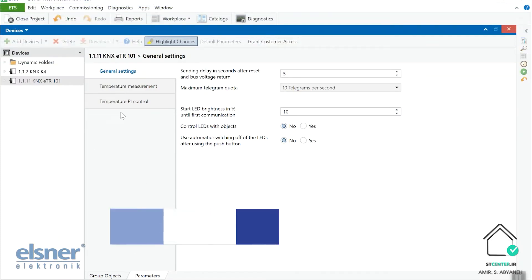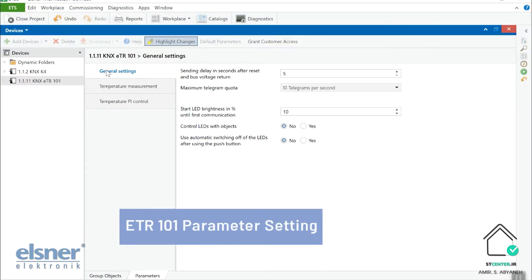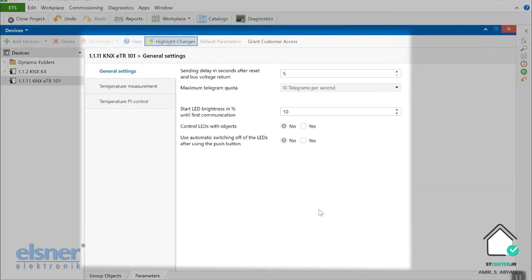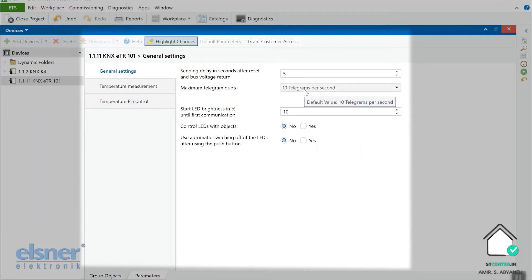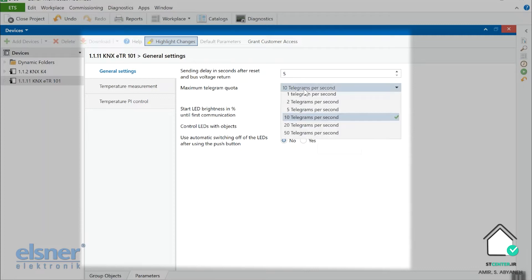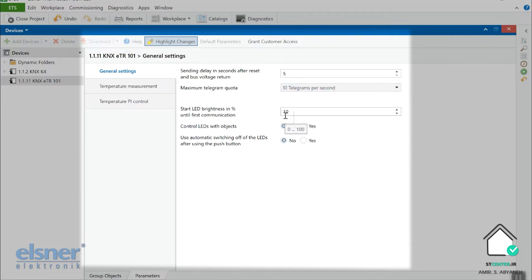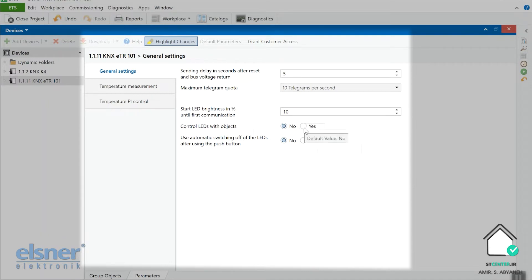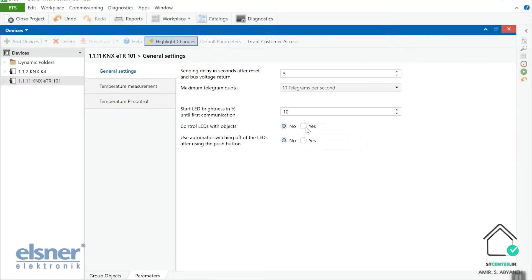In ETS in parameter, the first page of KNX eTR is general setting. In general setting you can assign the traffic of the data. So how frequently you want to send the telegram. I leave it as default. Also you can make a decision about the LED brightness. So when you increase the LED brightness, of course you use more power, but maybe you need it in some rooms with so much light. And also you can control the LED brightness with an extra object. That is awesome in my opinion. And also you can tell the device to turn off in automatic operation when you do not use it.